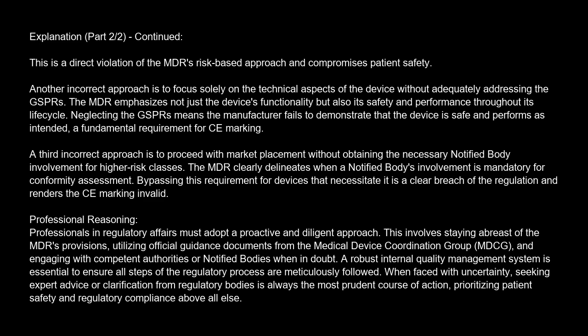Another incorrect approach is to focus solely on the technical aspects of the device without adequately addressing the GSPR. The MDR emphasizes not just the device's functionality, but also its safety and performance throughout its life cycle. Neglecting the GSPR means the manufacturer fails to demonstrate that the device is safe and performs as intended, a fundamental requirement for CE marking.